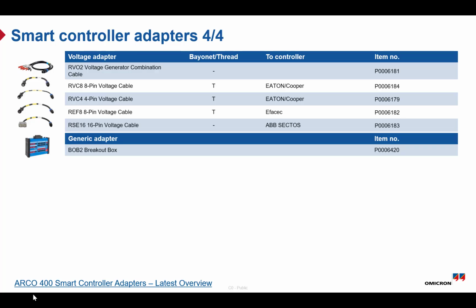Now, let us look at some additional adapter options. In some cases, you may need a voltage adapter. This is used when voltage signals or VTs are connected separately to the controller and not through the main control cable. It allows you to properly inject the measured voltage signals during testing.